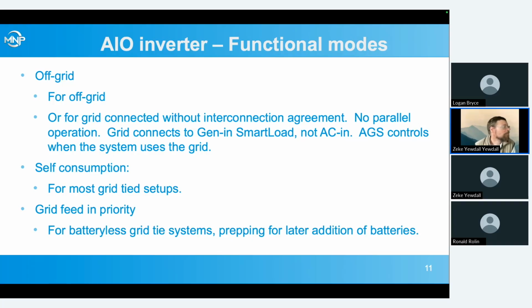For self-consumption, this is usually the best one for most grid-tied setups, even if you're not really wanting to use the batteries. And we'll talk a bit more about this on the next slide. Grid feed in priority. This is really just for batteryless grid tie systems. If you're wanting to add batteries later and you're using one of our inverters just basically as a straight grid tie inverter with no batteries, with the intent to add batteries later. You can also use it for grid tie systems with batteries, but it's got some issues that I feel are better solved by setting it for self-consumption and programming that.